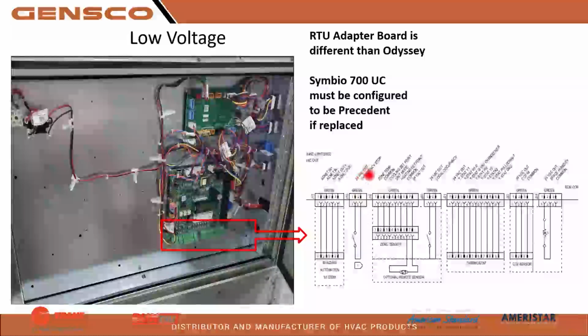Here's our, I'll dive back into this, but this is your 24 volt out. This is the J18 right here. That is for your duct supplied smoke detector or any kind of emergency stop. That is your E-stop. So remember that, because this is a normally open contact right here. If you wire anything into the 24 volt E-stop, you will have to go inside the app, and I got a slide showing it, to reverse connection polarity, and it will be a normally closed contact at that point in time, and you can hook it up to a normally closed safety device.